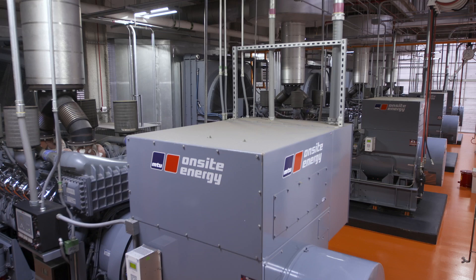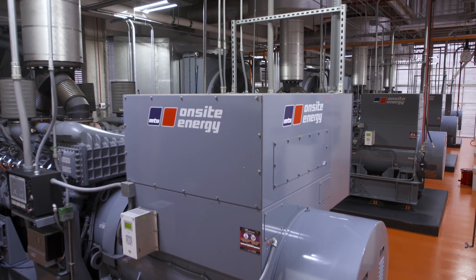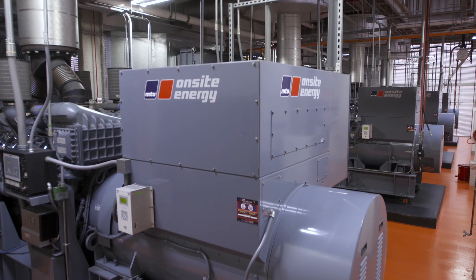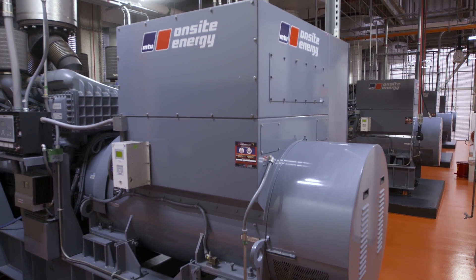If we were to lose power here at Nemours, we're technologically advanced enough with this building that as a facility manager, I sleep very well at night. Nemours ended up installing four 2250 kW units at 12.47 kV. If three generators would fail, we still have the capacity to run the life safety systems for the hospital.